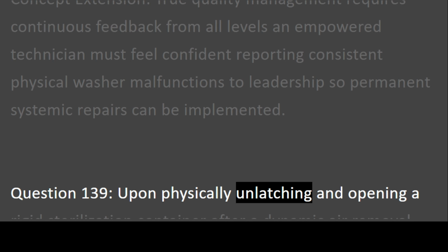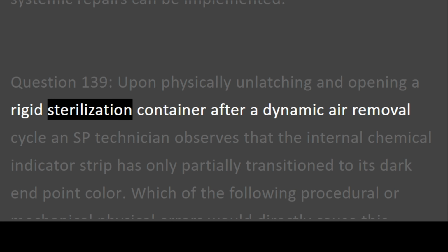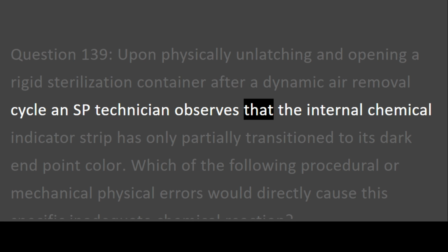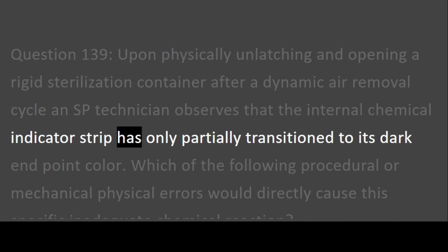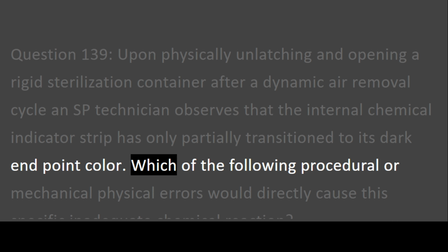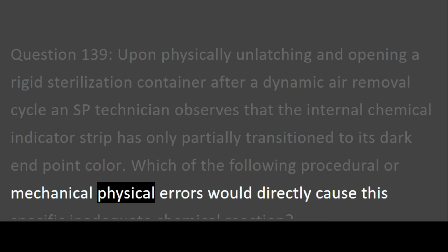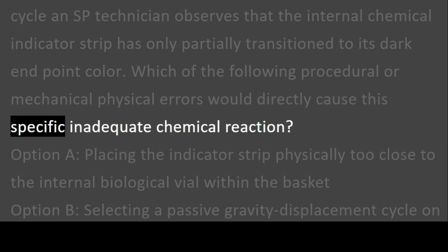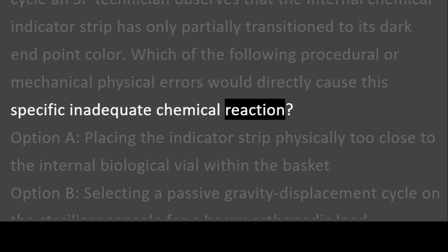Upon physically unlatching and opening a rigid sterilization container after a dynamic air removal cycle, an SP technician observes that the internal chemical indicator strip has only partially transitioned to its dark endpoint color. Which of the following procedural or mechanical physical errors would directly cause this specific inadequate chemical reaction?